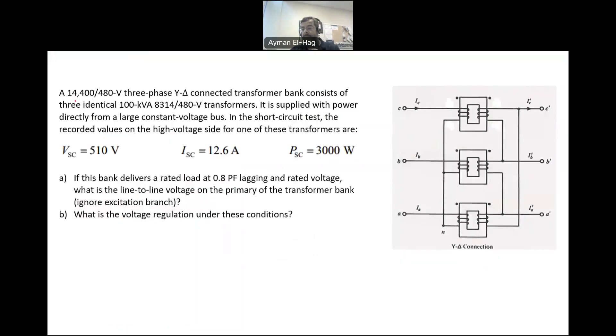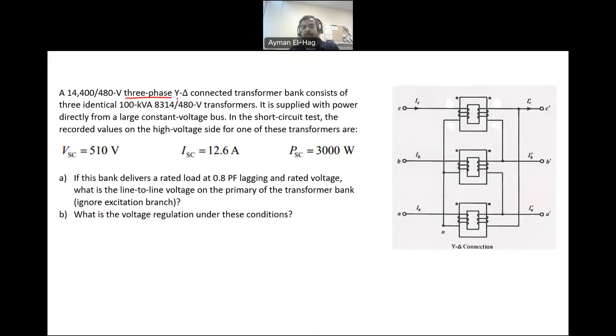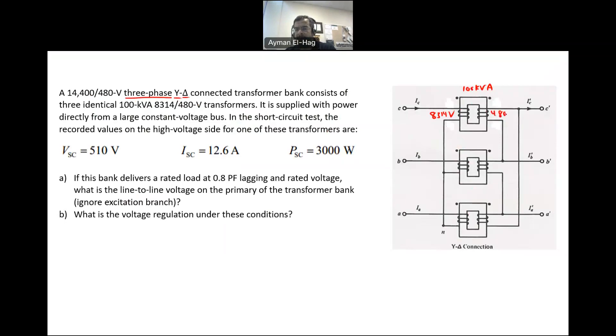The three-phase transformer primary voltage is 14.4 kV and the secondary voltage is 480 volts. When we are given the ratio as a three-phase, as mentioned here, we are given the ratio of the line-to-line voltages. This transformer is Y-connected in the primary and delta in the secondary. It is connected as transformer banks — we have three transformers, each one is 100 kVA. The turns ratio of the single-phase transformer is 8314 volts in the primary and 480 in the secondary.